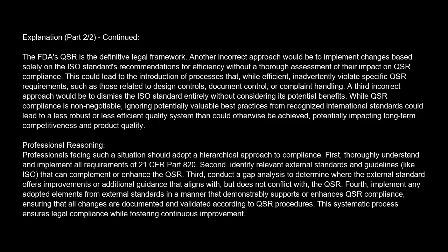Professional reasoning. Professionals facing such a situation should adopt a hierarchical approach to compliance. First, thoroughly understand and implement all requirements of 21 CFR Part 820. Second, identify relevant external standards and guidelines, like ISO, that can complement or enhance the QSR.